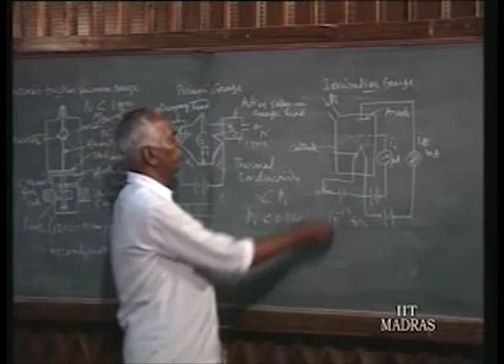It is a battery, and the grid circuit has its own circuit, and from cathode to anode we have another circuit. So the anode is positively charged with reference to the cathode, and the grid is negatively charged with reference to the cathode. These are independent circuits, three independent supplies we have got. The gas molecules, or the vacuum to be measured, are allowed here, and they will occupy the space inside the tube. And when we heat this cathode element, electrons will come out.